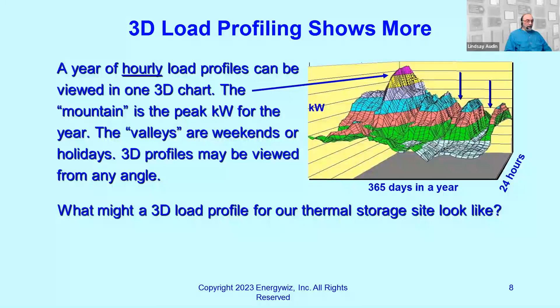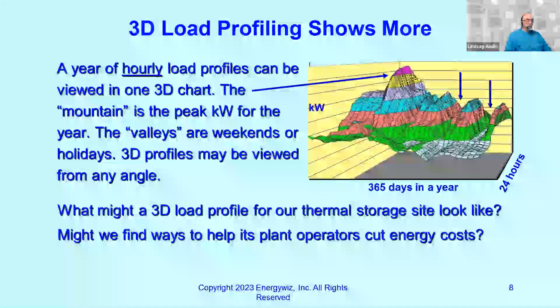In this case, our mountain peak is the peak kW for a year. The valleys, those are your weekends or holidays. You can look at these 3D profiles from any different angle, and we are going to flip this around to get a better look at it. So if we have this understanding of an entire year's load, or at least the time of the cooling season, how could we use this to understand thermal storage? And are there ways in which we can look at this kind of information to help our plant operators cut their energy costs?